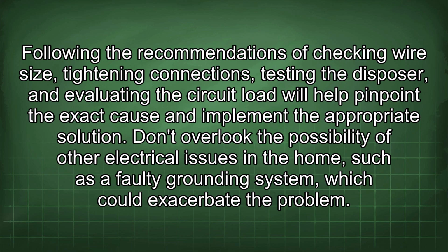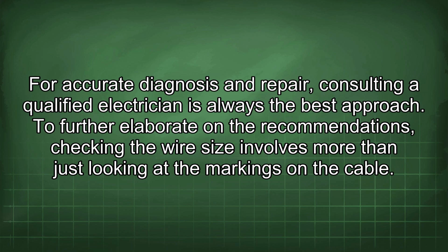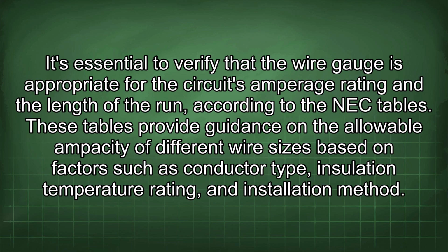Don't overlook the possibility of other electrical issues in the home, such as a faulty grounding system, which could exacerbate the problem. For accurate diagnosis and repair, consulting a qualified electrician is always the best approach. To further elaborate on the recommendations, checking the wire size involves more than just looking at the markings on the cable. It's essential to verify that the wire gauge is appropriate for the circuit's amperage rating and the length of the run, according to the NEC tables. These tables provide guidance on the allowable ampacity of different wire sizes based on factors such as conductor type, insulation temperature rating, and installation method.